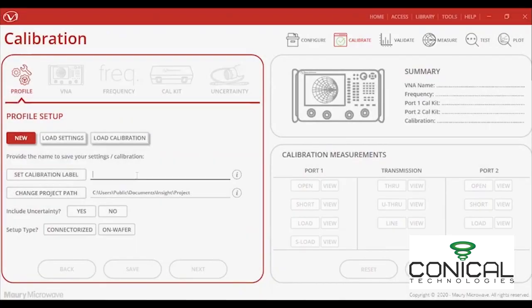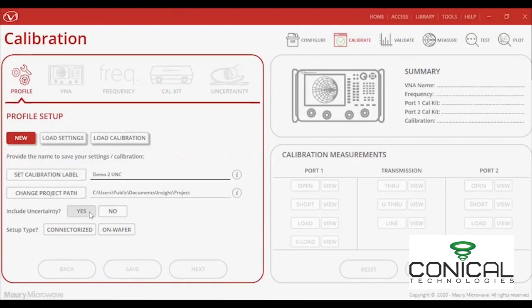First, let's take a look at the Profile Setup tab, where the user can either create a new calibration profile, load an existing profile, or load an existing calibration. This can be very helpful to replicate identical setups regardless of the person driving the software. You can also choose whether to include uncertainties and if your measurements will be coaxial or on wafer.